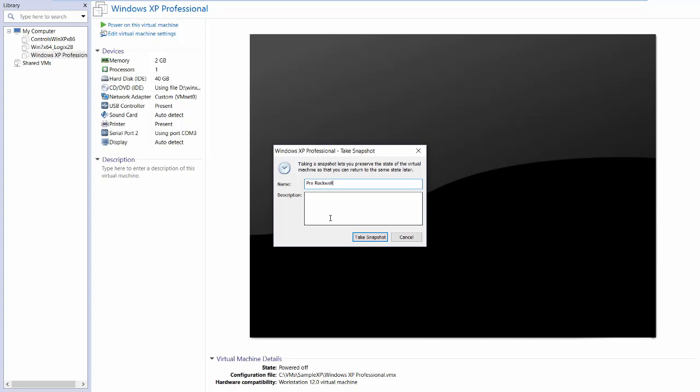And another good thing to pay attention to here is I've already installed drivers for the different kinds of USB dongles that I think I'm going to use for serial and RS-485 and Data Highway. If you plan on installing other software packages that aren't, say I'm going to do Rockwell and I'm going to do Omron and I'm going to do GE. I think it's a good practice to keep those separate. And again, I'll talk about this more later. But to avoid installing those drivers three different times, I'm going to install them first and take this snapshot after I've installed those.